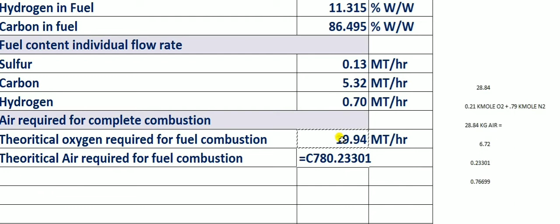So percentage excess air. Actually, we supplied excess air for complete combustion, correct? So percentage excess air we already calculated in the previous video. Same thing: O2 in flue gas divided by 21 minus O2 in flue gas, where 21% is the O2 content in ambient air, into 100 is the percentage excess, right?